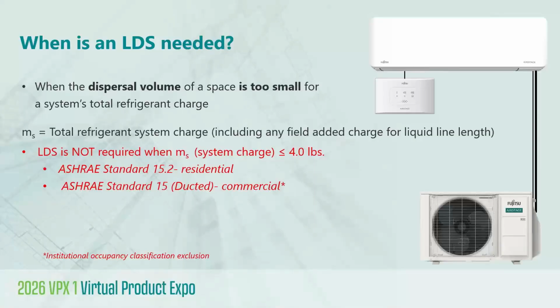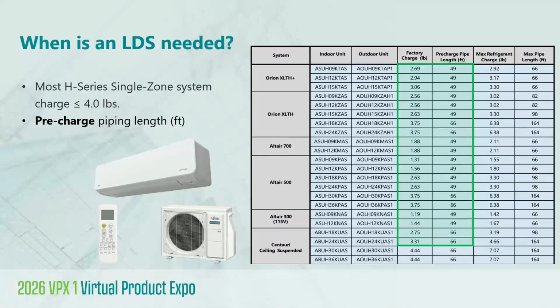That 4 pound threshold becomes significant because it means that many of our H-Series systems are already refrigerant charge compliant right out of the box. It's a claim I like to often boast about, but instead of relying upon my words alone, let's look at some actual charge data and see how the numbers support that. The table you're looking at on the right is an excerpt from one of our more popular application bulletins for navigating compliance requirements. Internally, we like to call it our cheat sheet, and we have one available for both commercial and residential standards.